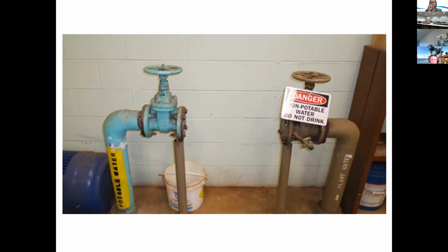And at first you think, okay, that makes a lot of sense. But then you start thinking, well, what if the reclaimed water system went down, or part of the filtering system went down and it wasn't a high enough quality reclaimed water to be used in the plant anymore? And you start looking, and on the other side of this bookshelf, they still had the backflow device sitting on the floor.